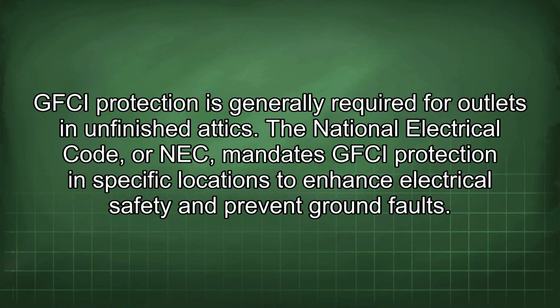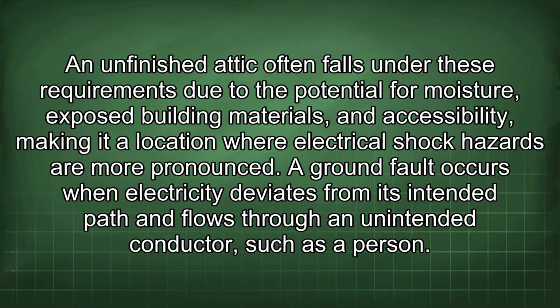GFCI protection is generally required for outlets in unfinished attics. The National Electrical Code, or NEC, mandates GFCI protection in specific locations to enhance electrical safety and prevent ground faults. An unfinished attic often falls under these requirements due to the potential for moisture, exposed building materials, and accessibility, making it a location where electrical shock hazards are more pronounced.